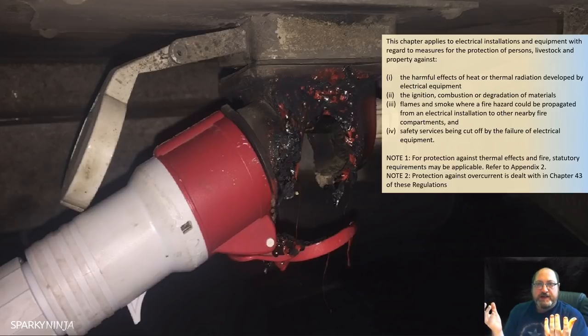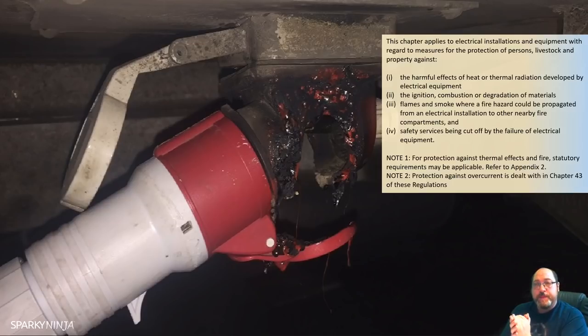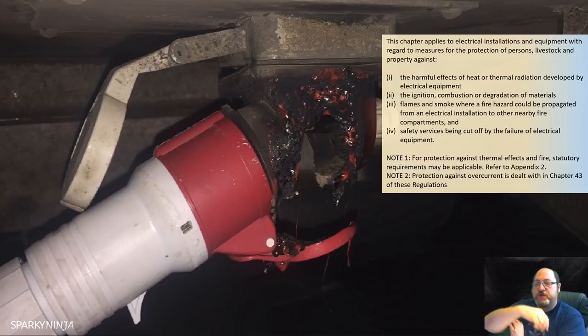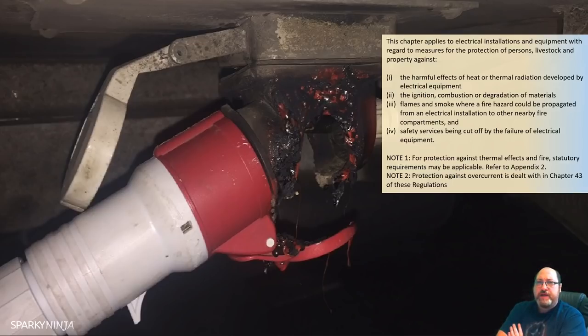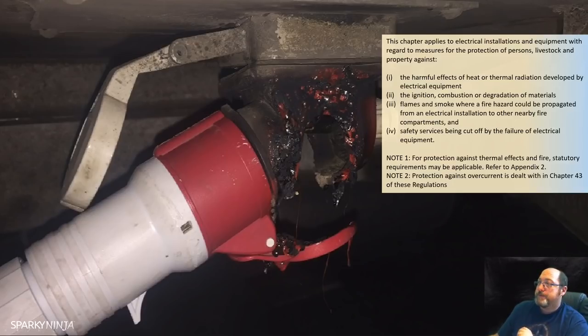Most times these days, especially in small-scale shops and pubs, emergency lighting will be self-contained within the luminaire — that's fine because there's no separate wiring system. But if instead we had a battery bank or a standby diesel-driven generator, that lighting distribution system — which you see in older buildings and sports centres — has to be installed so its life won't diminish. We must consider the potential thermal effects that can occur to safety services and ensure they're not cut off.